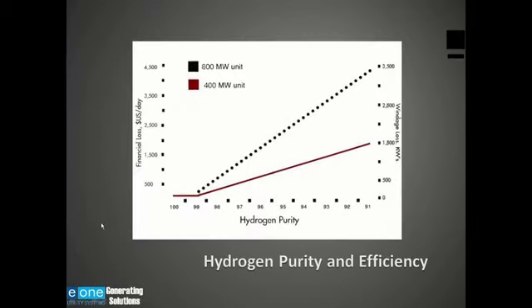From this chart, we can see how hydrogen purity affects windage losses, which has a direct effect on financial losses. You can see if my purity is in the neighborhood of 91%, I've got 1,500 kilowatts in windage loss. However, if I'm operating in the neighborhood of 98, 99%, my windage losses go down close to zero. And this has a direct effect on financial losses, or how much it costs to generate power.